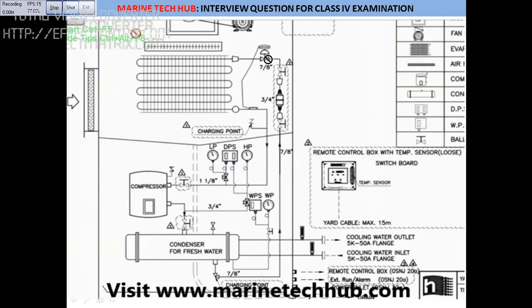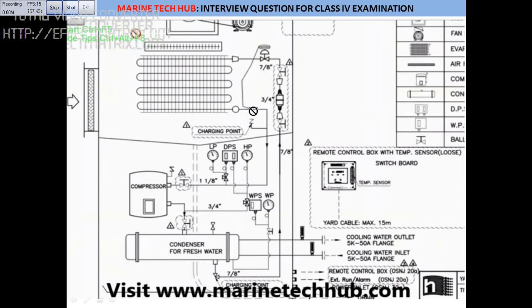From the expansion valve, the liquid will turn into gas, and this is the evaporator. Normally, the question they will ask is about the bulb — the bulb of the expansion valve is connected at the outlet of the evaporator. This should not be loose; if it is loose, it will not sense properly. The purpose of the bulb is to make sure liquid is not going into the compressor — if liquid is coming, it will sense and close the valve. The gas will then go through the evaporator, where a fan blows air through.